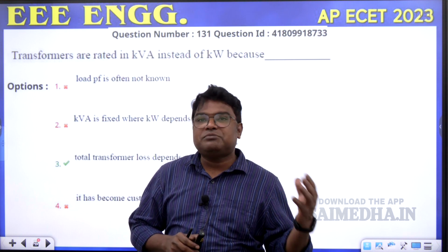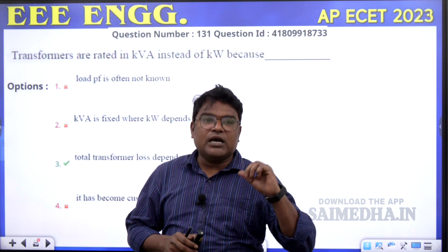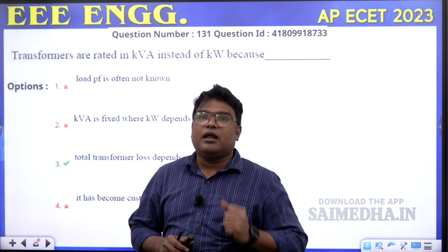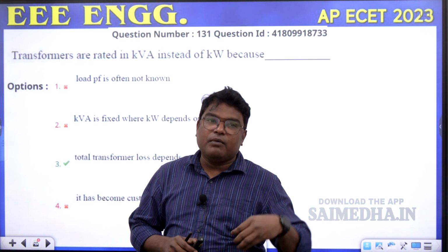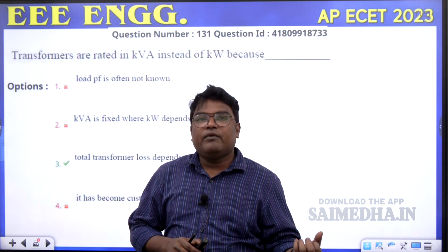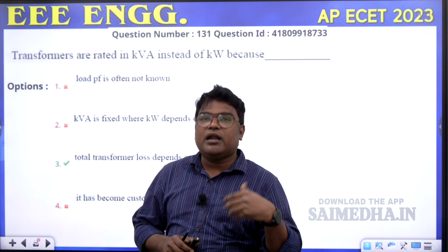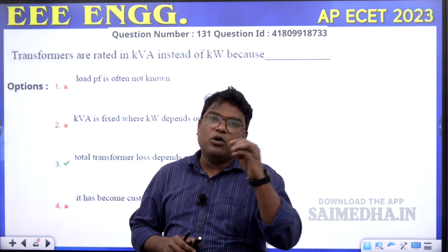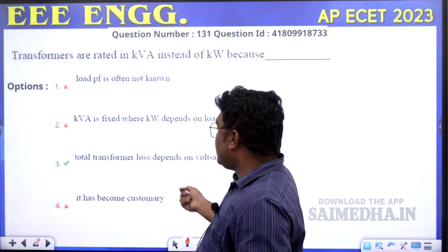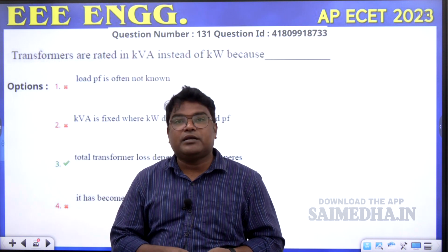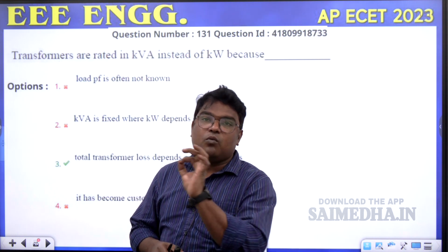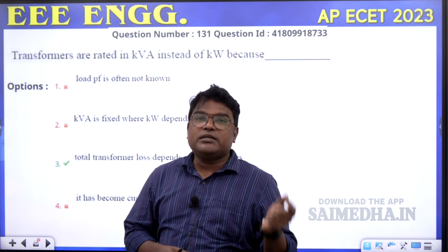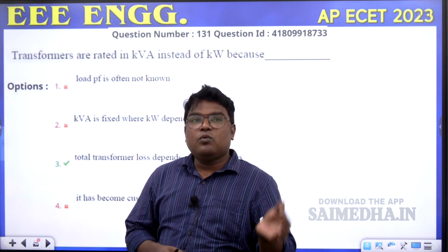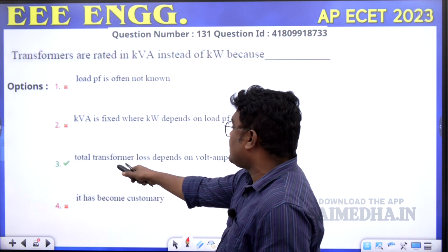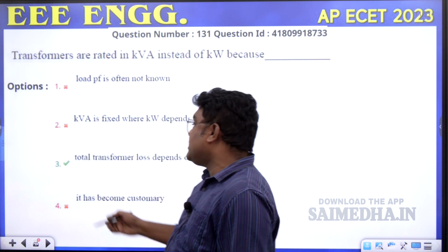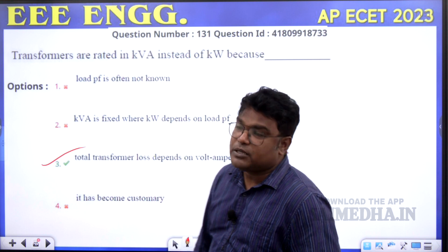Majorly we have two types of loss in the transformer: copper losses and iron losses. Iron losses represent the voltage parameters, and copper loss depends on the current parameters. The iron loss depends on the voltage, whereas copper loss depends on the current. So the transformer loss depends on the volt-amperes. So option 3 is correct for this question.